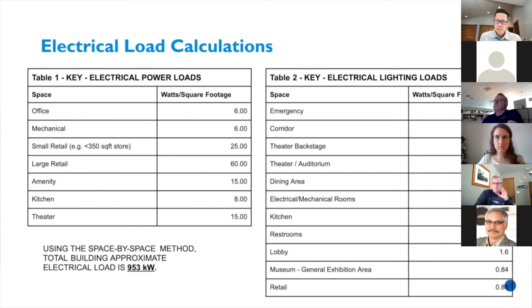For example, in Table 1 we can see that an office space typically has a power load of 6 watts per square footage. Multiplying that by the square footage of a space gives the total electrical power load. Using the square footage of different spaces in our building, provided by the architects, along with the two tables, we came up with a total building approximate electrical load of 953 kilowatts.